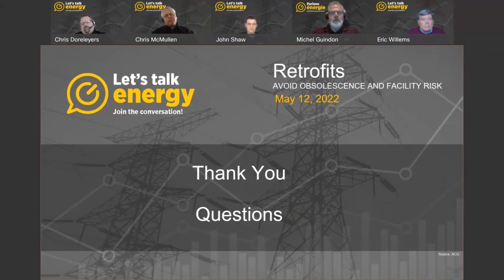Cummins comes to mind with their Power Command controller, which is a fully integrated controller. They've done a great job making this one proprietary. It's very difficult to put a non-Cummins unit into that because the governor and voltage regulator are integrated with the controller. That's the only one we've run into roadblocks on, but even the older Cummins units that didn't have that type of integration were no problem in upgrading.